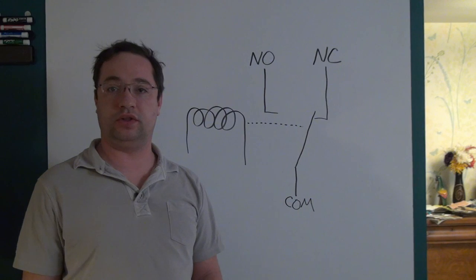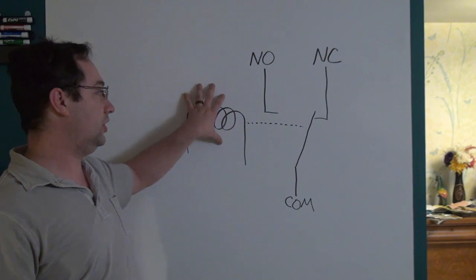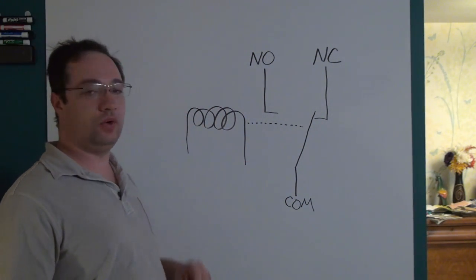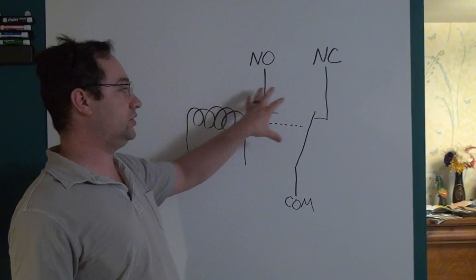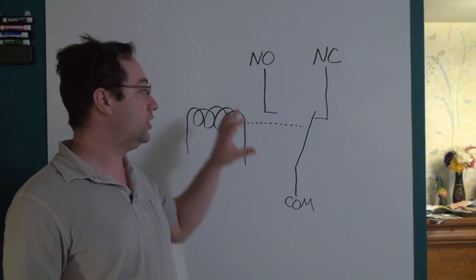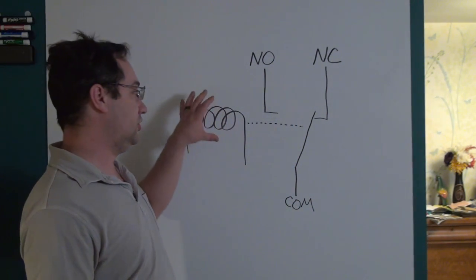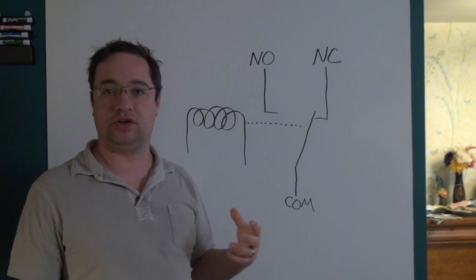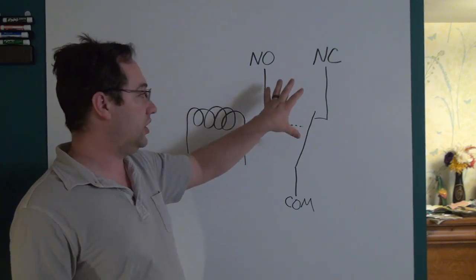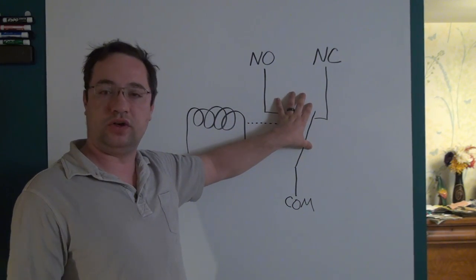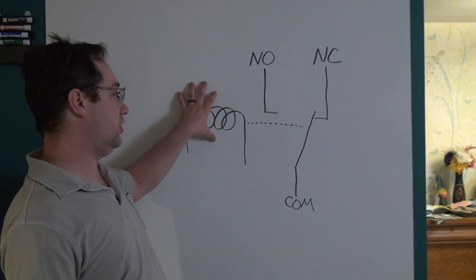When talking about relay ratings, we work from left to right. The left side, with the coil, is called the control side, because it causes things to happen. The right side is called the hot side, because the voltage and current can be tremendously different — you can have hundreds or even thousands of volts on the hot side being controlled with just 12 or 24 volts on the control side.